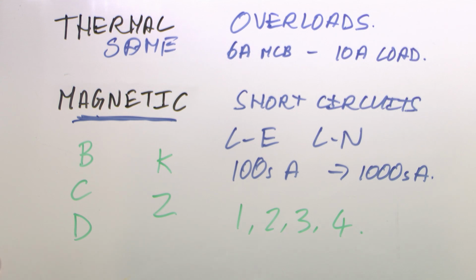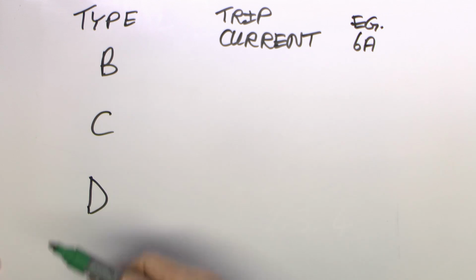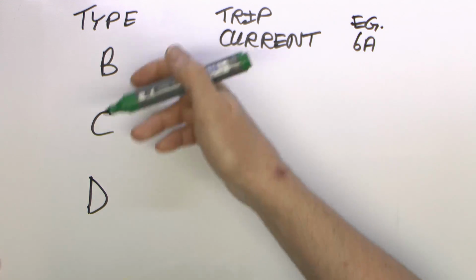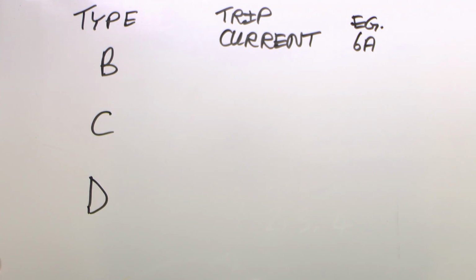They're still relatively common, and you can still keep using these. There's no reason not to. It's just that this is a different rating system to the letters we've got over there. Now, I'll have a look at the three most common types, which are B, C and D. I'll have a look at the other ones a bit later on. Now, the letters indicate the trip current that the particular circuit breaker will trip at.